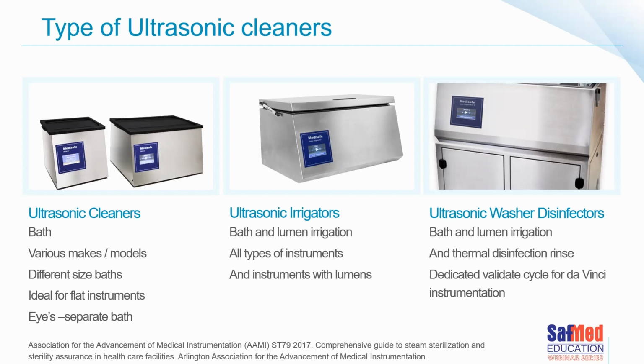Then we can get ultrasonic washer disinfectors, so baths with lumen irrigation and a thermal disinfection rinse. Why is that so exciting? Well, a thermal disinfection rinse, of course, makes it a bit safer to manage the instruments afterwards. That rinse normally is around 90-odd degrees. Again, far better for us to handle instruments that have gone through a thermal disinfection rinse cycle. Often these types of devices may have a dedicated cycle for things like da Vinci instrumentation.